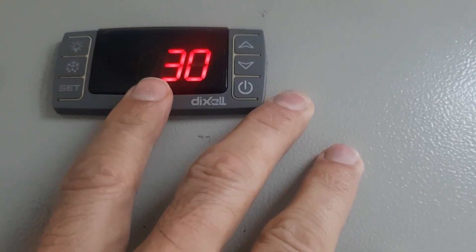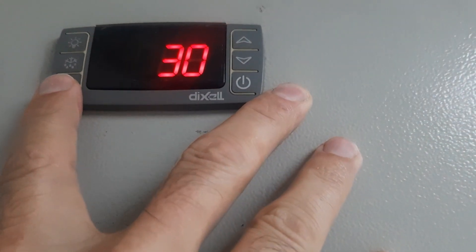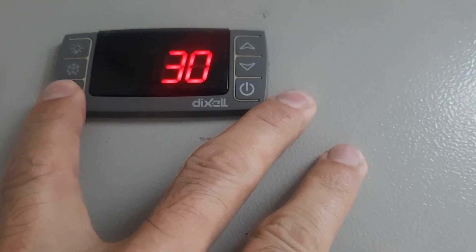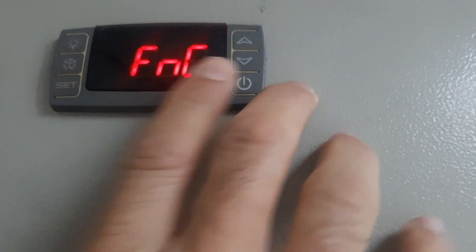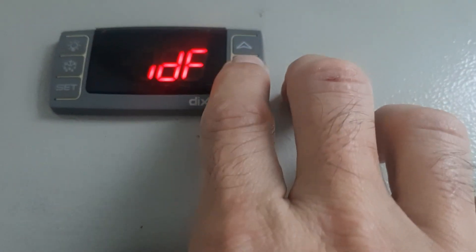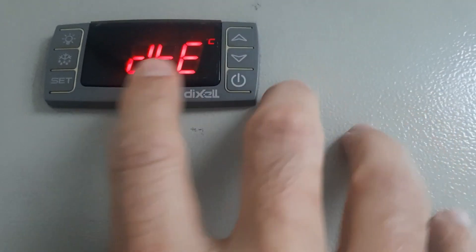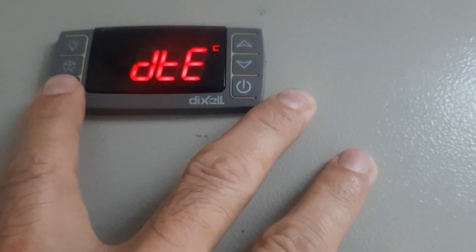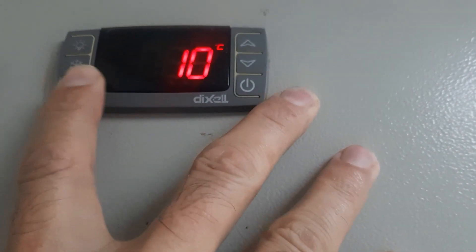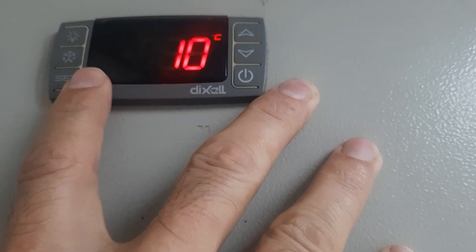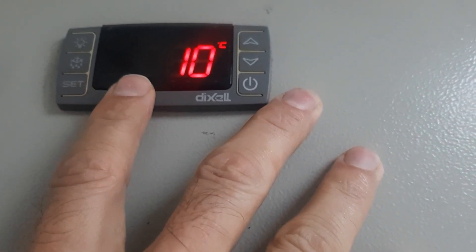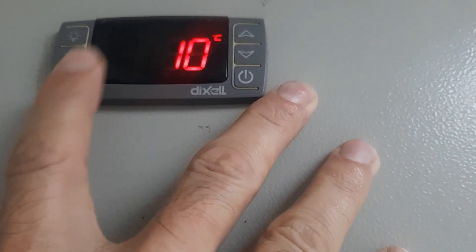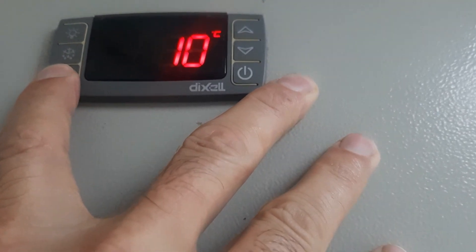After that we have other option for temperature, I will show you DTE, defrost stop temperature. This is 10 degree. When the evaporator sensor temperature goes above 10 degrees, the defrost will terminate.